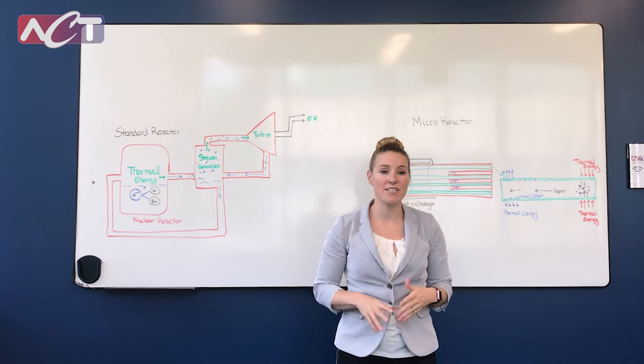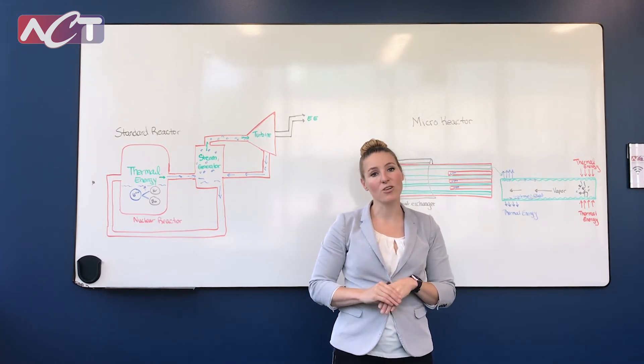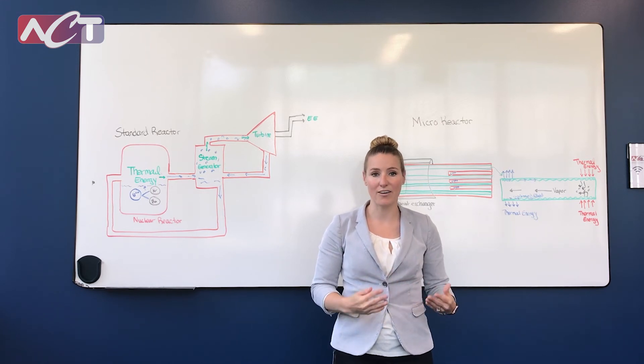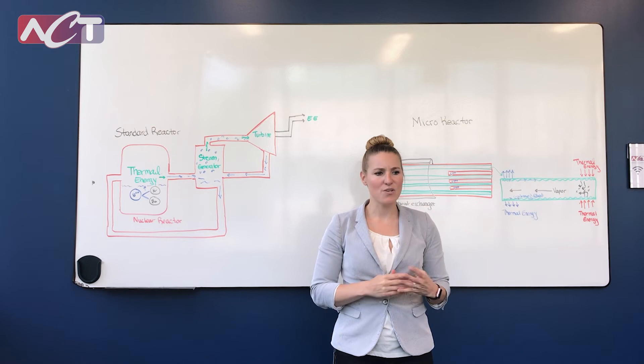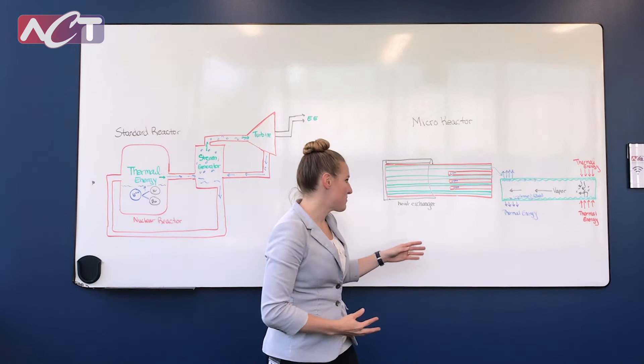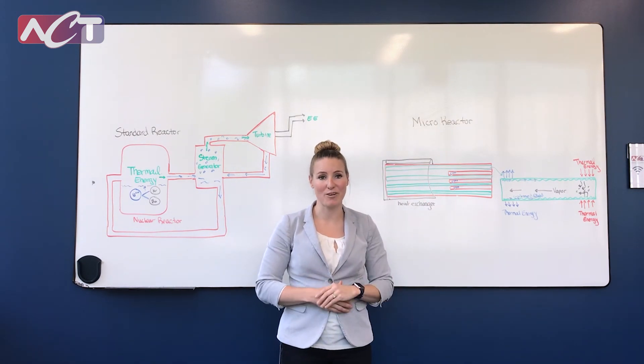The condensed fluid then returns back to the hot spot, either via gravity or capillary action of that wick structure. We'll pick a working fluid based on the temperature of the operation. For nuclear, we're looking in that 650°C range, which typically uses some form of alkali metal, like sodium or potassium. This operates in that widely accepted nuclear range and is most commonly used in these types of micro reactors.